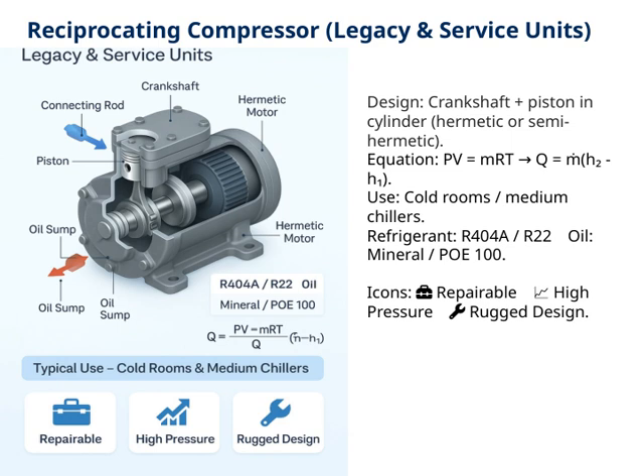This design has been reliable and well understood over the years. In terms of the fundamental principles, the operation is based on the ideal gas law, PV equals mRT, which relates pressure, volume, and temperature. When it comes to cooling capacity, we often look at the heat transfer equation, Q equals the mass flow rate times the change in enthalpy, or ṁ times (h2 minus h1). This helps us understand how much heat is being moved during compression.